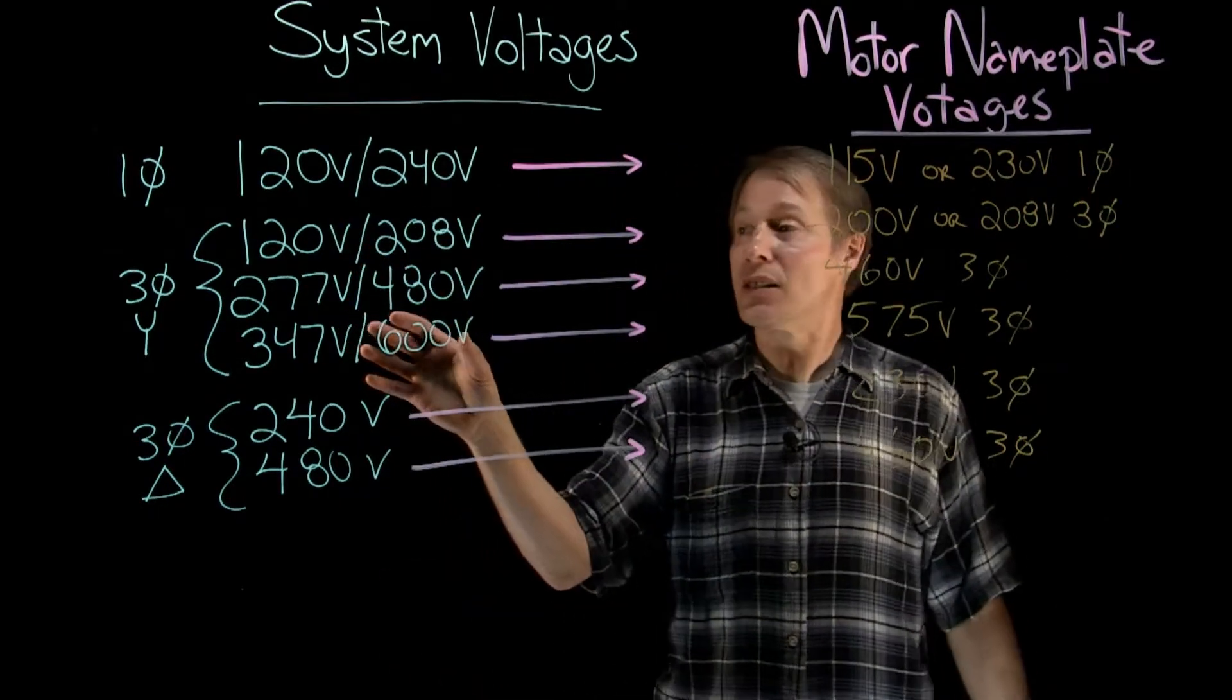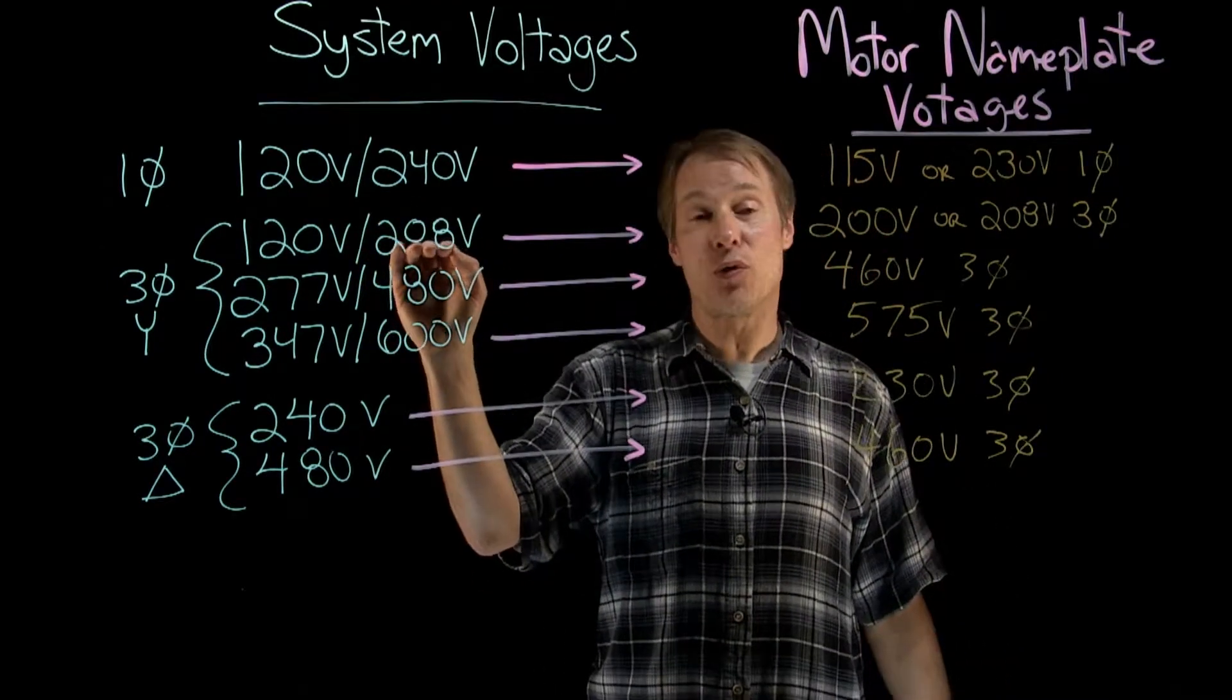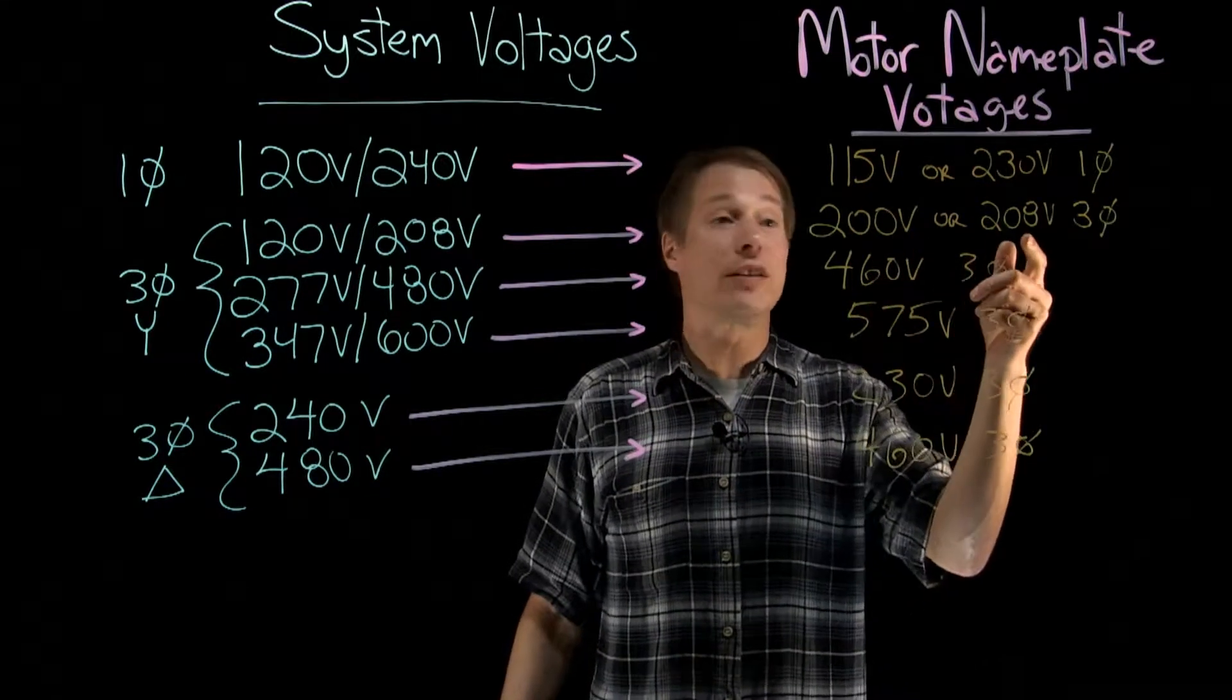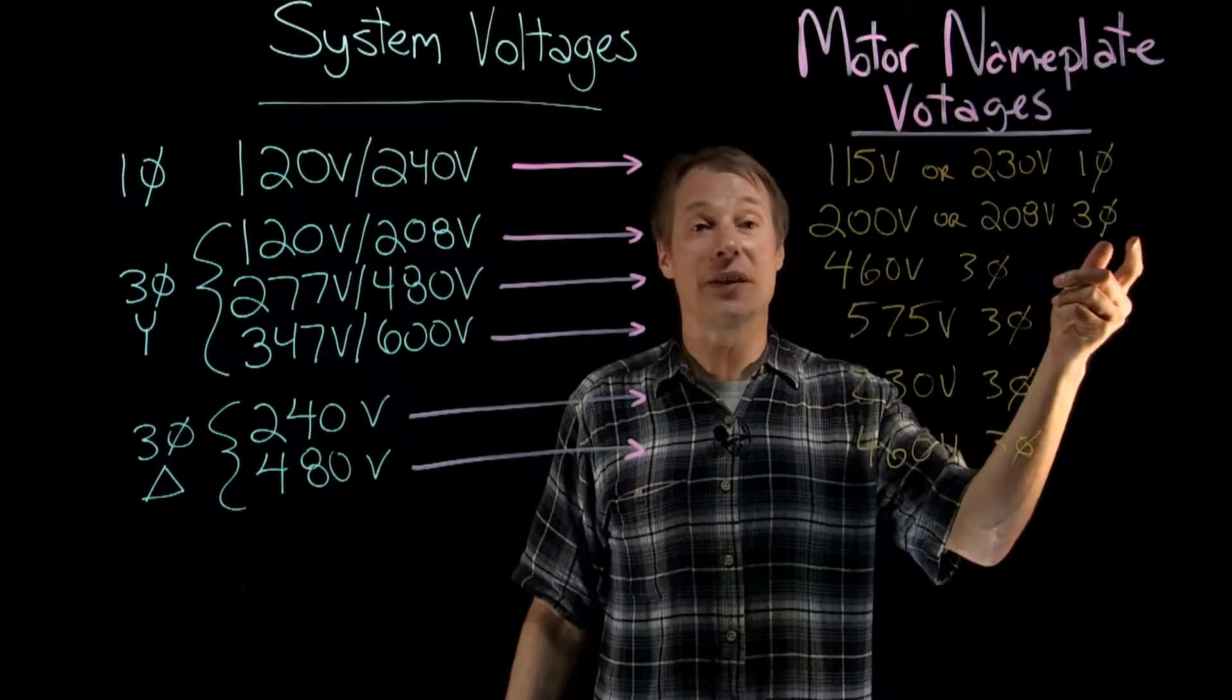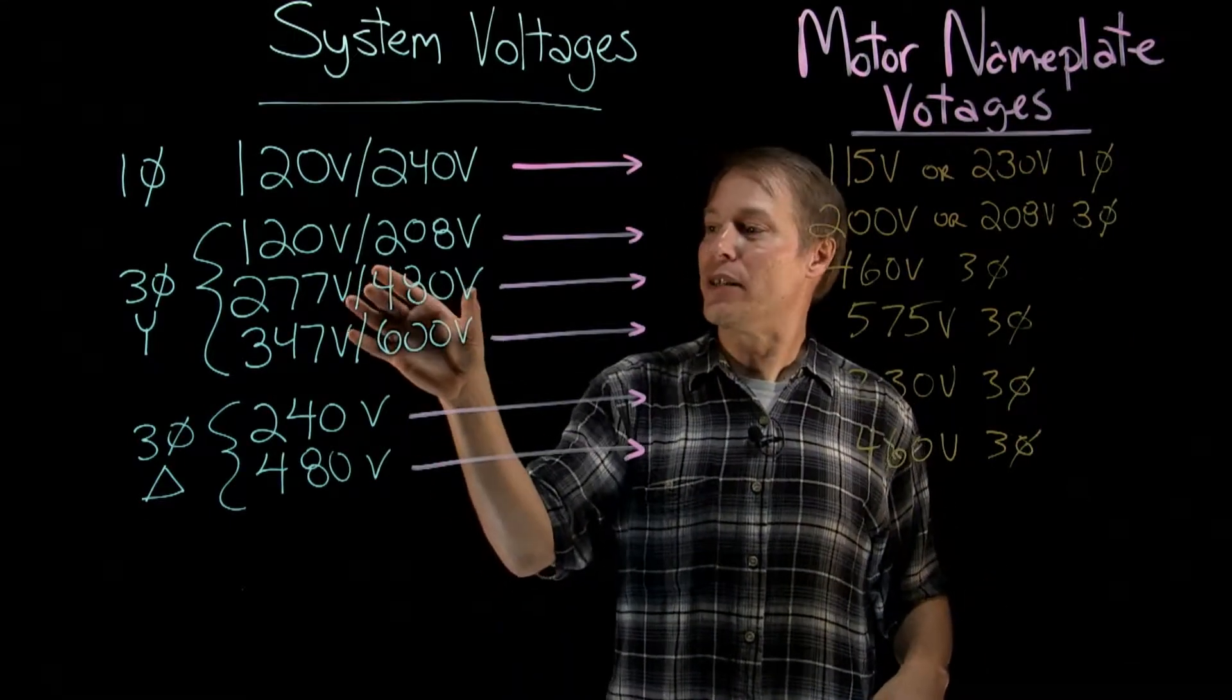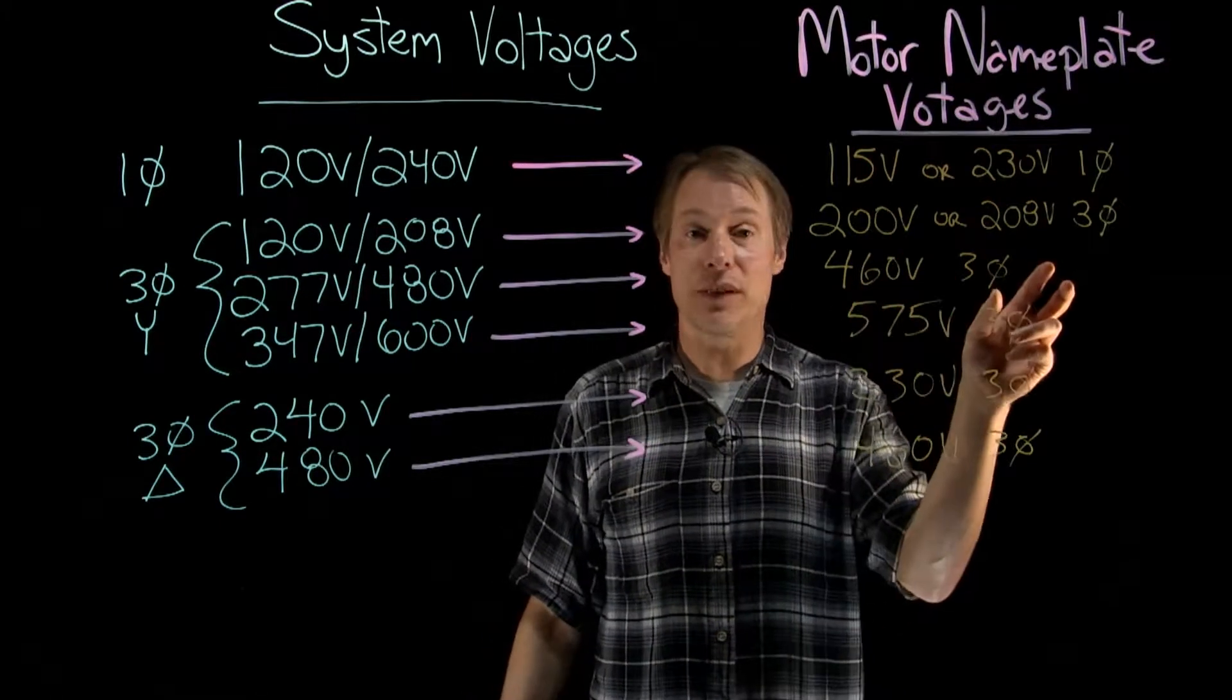Moving on to the commercial application, we're looking at these numbers here. So for a 208V system, we're looking at a 200V motor or a 208V rated three phase motor. The rest, you can probably see what's going on here. So for a 480V system, we're looking at a 460V three phase motor. For the 600V three phase, we're looking at a 575V three phase motor.